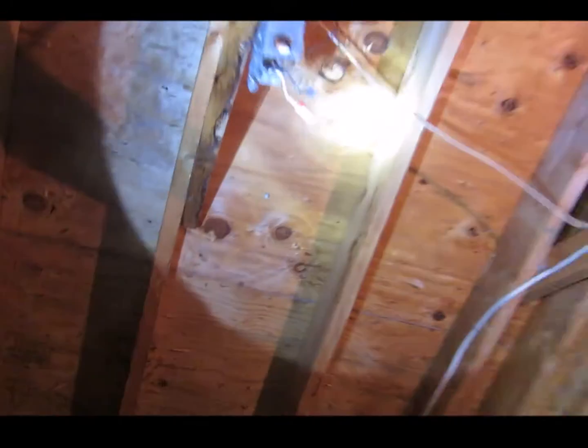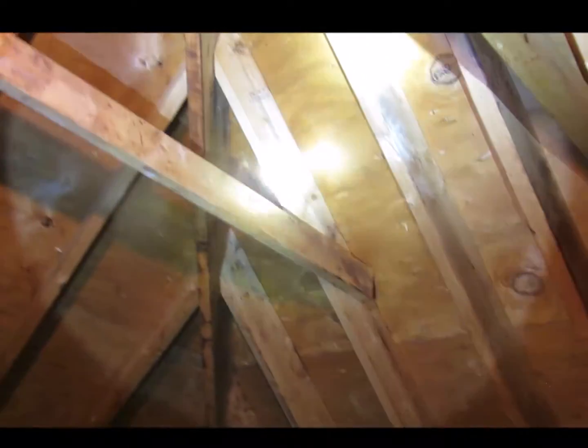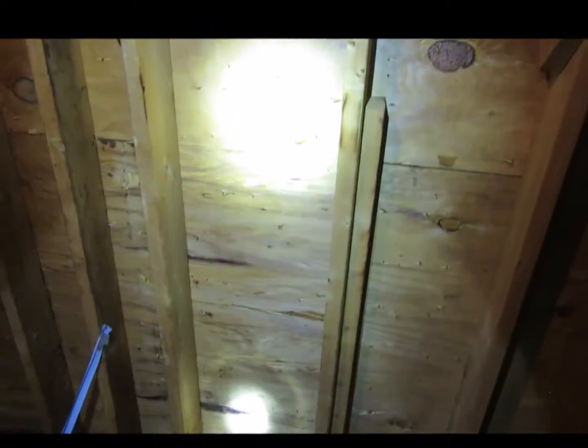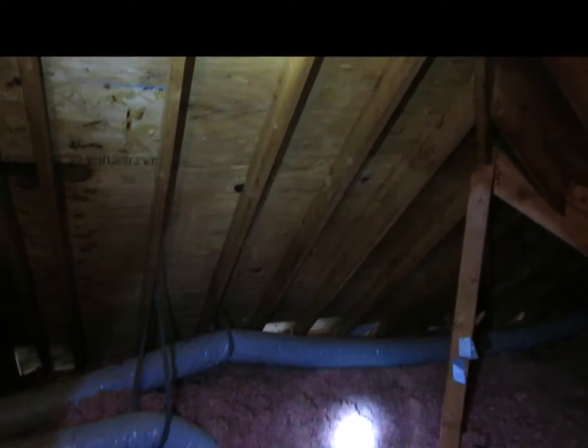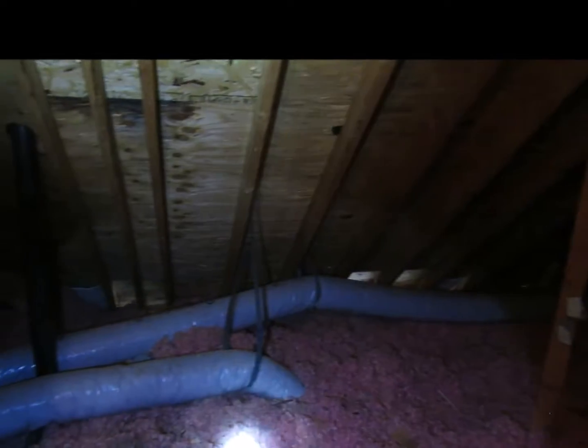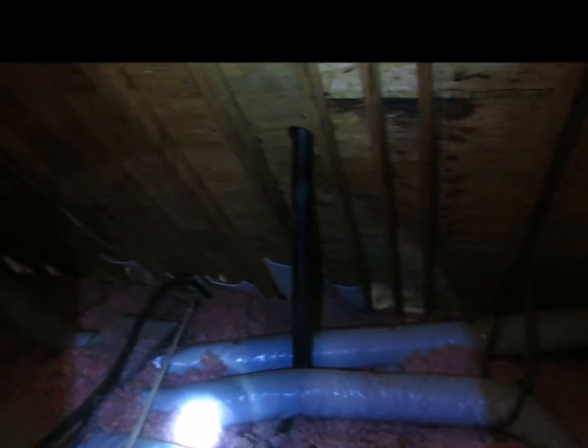We have a control here for a fan, but there's no fan hooked up to it. So when I look at the wood, I see a fair amount of amber color. This indicates that this roof gets very hot during the summer. And I see why now, because there's no passive ventilation in this attic. So when this gets superheated, then that heat is transferred into the ducts and into the insulation and then into the ceiling below.